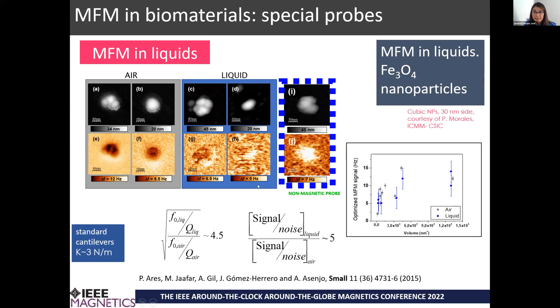It's a problem due to the decrease of the quality factor of the lever when we measure in liquid media. So we have a signal-to-noise ratio nearly 5 times worse when we measure in liquid than in air. So we need to develop specific MFM probes if we want to enhance the signal-to-noise ratio to measure the same signal in liquid media. We can perform a study of fundamental MFM noise, and we can achieve a theoretical signal-to-noise ratio improvement of nearly a factor of 4 if we use specifically designed cantilevers, the so-called biolevers, with a smaller spring constant to measure magnetic signal in liquid, but they are not available on the market.